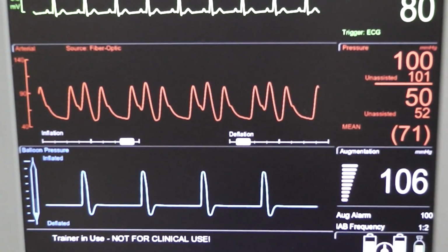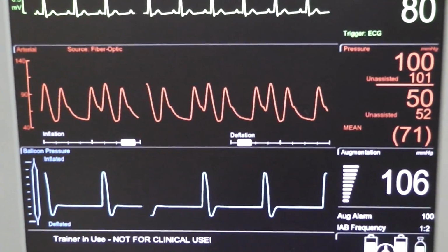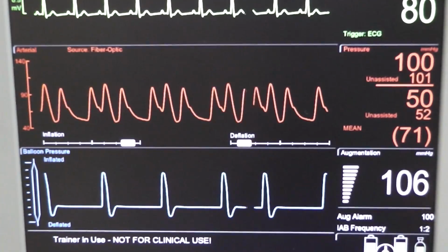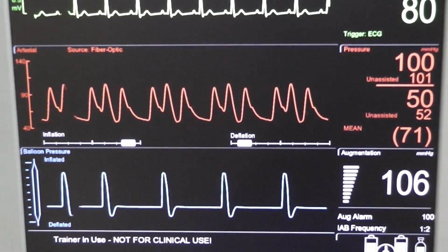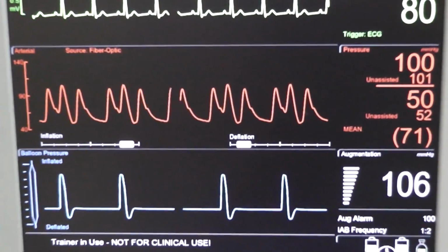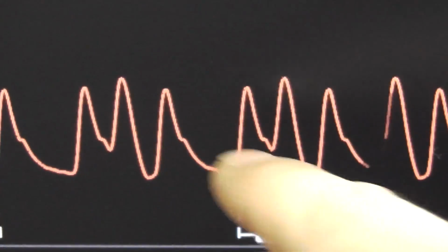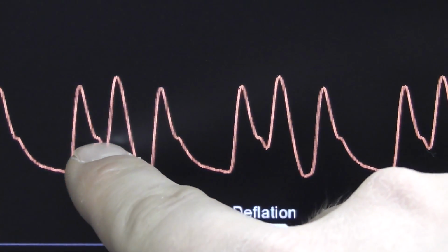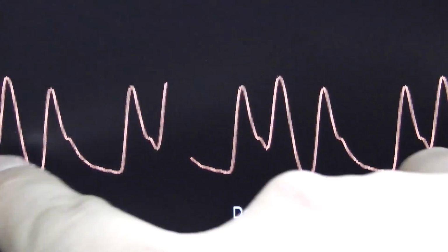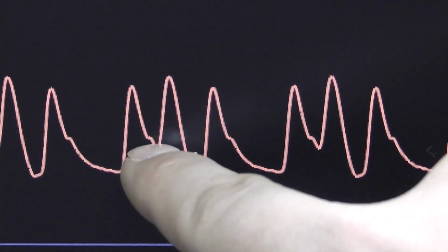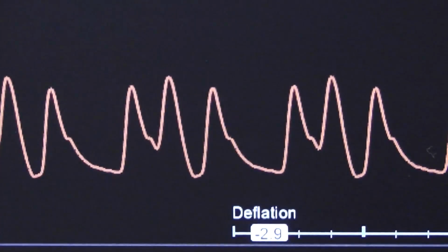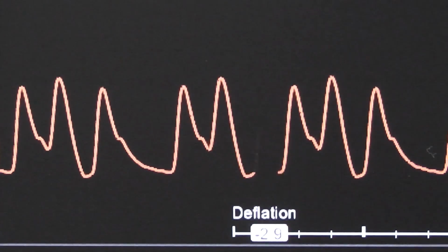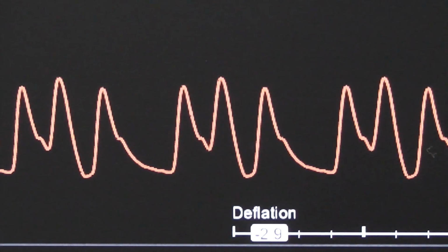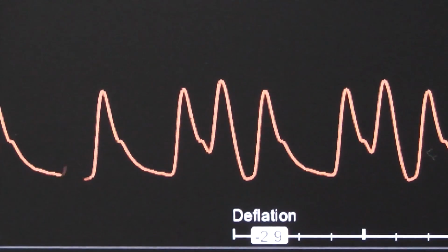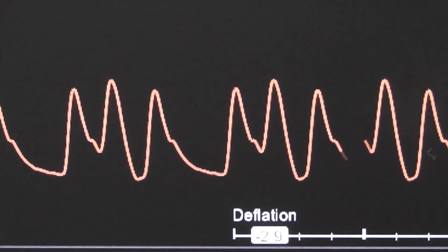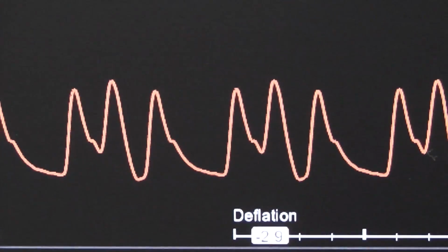It's not really going to do much to augment them at this point, but it's a good, safe starting point. Now, the way we can adjust the inflation is we want the inflation to occur right at the dicrotic notch. So let me see if I can zoom in here. And you can see right here on the down slope, this is the, let me get on camera here, this is the dicrotic notch. And that's where we want the inflation point to occur. So I'm going to adjust that inflation timing so that it meets up perfectly with that dicrotic notch.